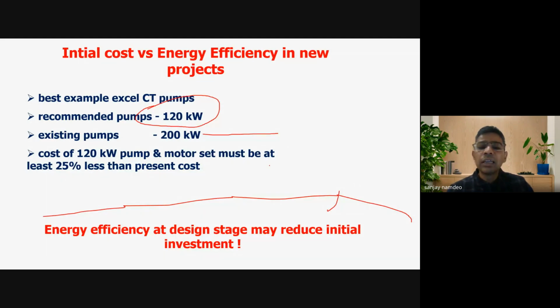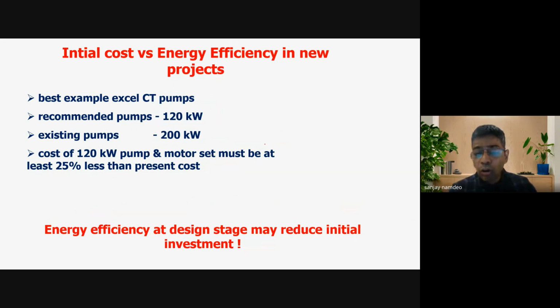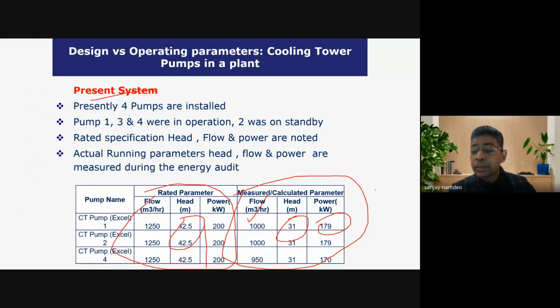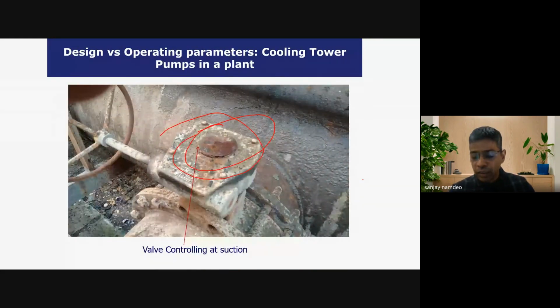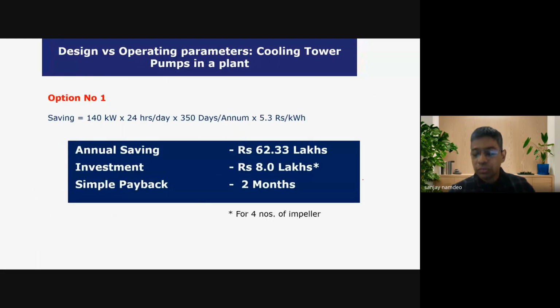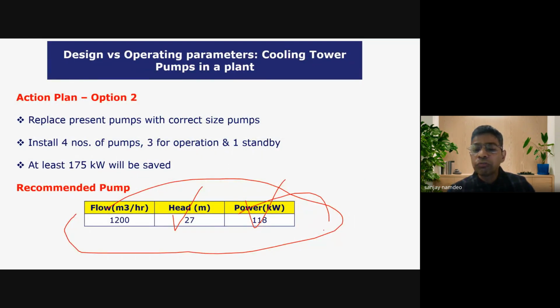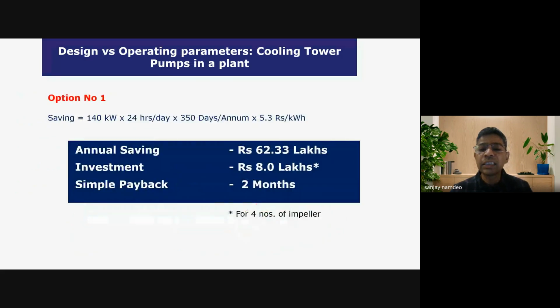So one gap is what? This higher capacity pump has cost us more, around 25% higher cost. Also, what is the gap? See, present power consumption is how much? 179 kilowatt. Had this been of the correct size, the power consumption would have been only 120 kilowatt. So 59 kilowatt of power difference per pump. And this 59 kilowatt of power difference is equal to around 62 lakhs per year, at a power cost of only 5.3 rupee, with this plant running 350 days per year and 24 hours per day.